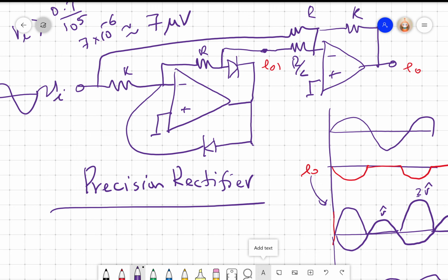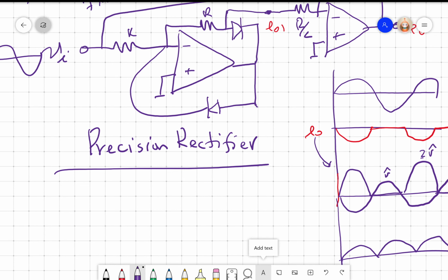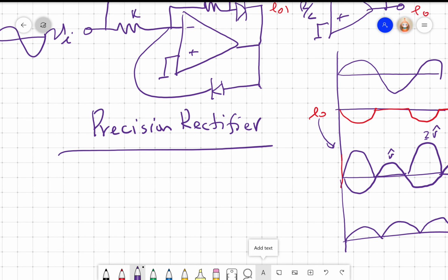And I can straight away get a DC output proportional to my plunger position L. And also the moment I rectify, please remember, even if I have a phase shift between E1 and E2, I am rectifying, converting it to DC, so my phase shift simply vanishes. At some point, I will get the DC of E1 equal to DC of E2, and they will cancel out and get a 0.